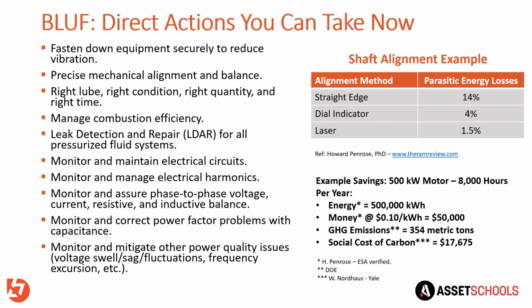And when we have a lot of nonlinear loads, it produces what are called electrical harmonics. And a harmonic is a multiple of the base frequency. So here in Australia, you're on a 50 hertz frequency. So your second harmonic would be at 100 hertz, your third would be at 150, your fourth at 200, your fifth at 250, so on and so forth. The reason that these are problematic is when you have voltage at these harmonics, measurable voltage at these different harmonics, you get what's called harmonic distortion. You get harmonic distortion in your systems. That means that the sinusoid no longer looks sinusoidal.